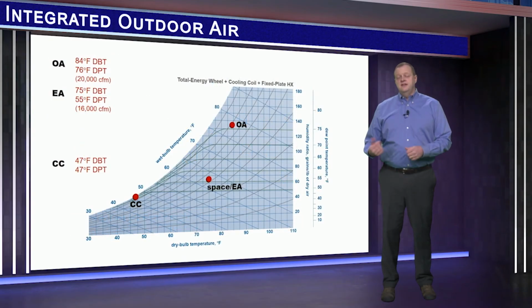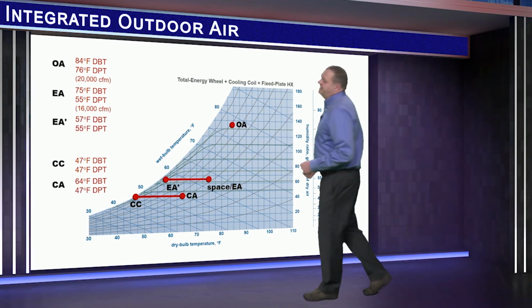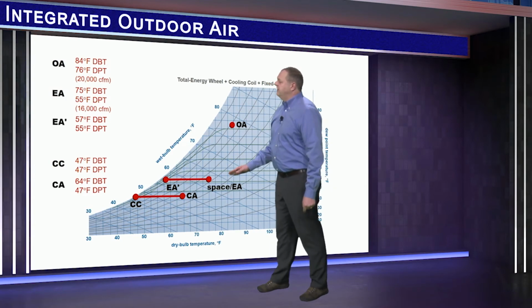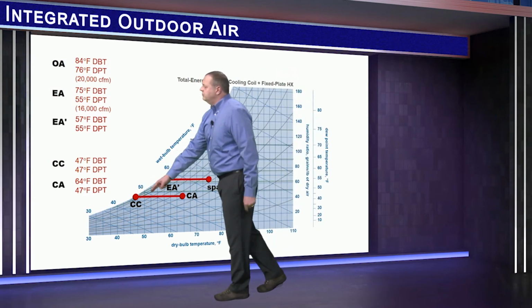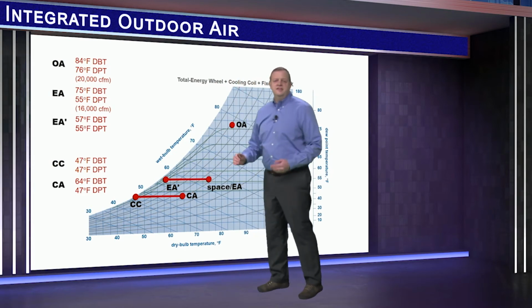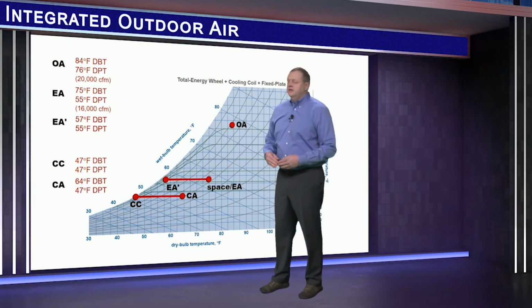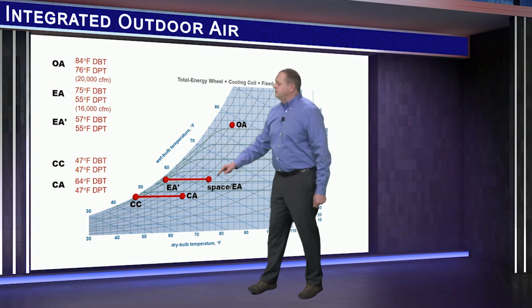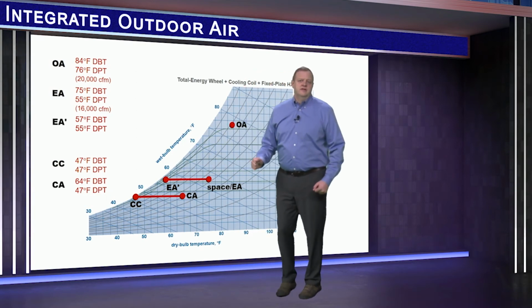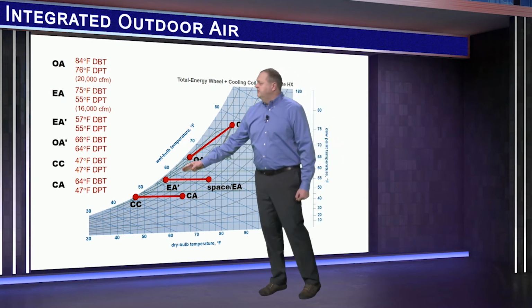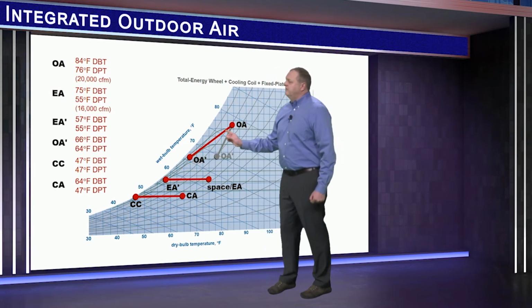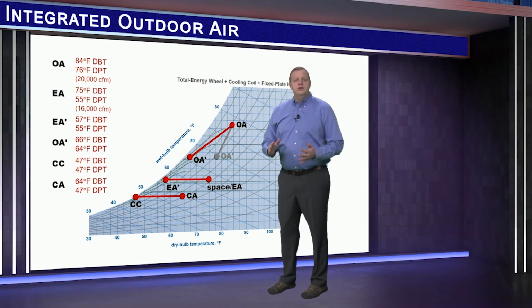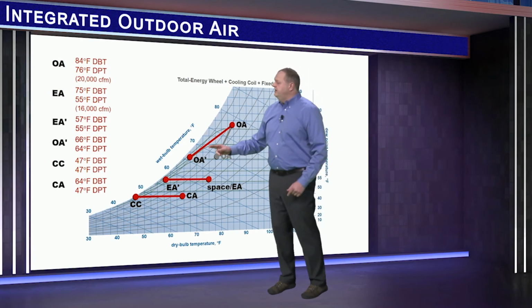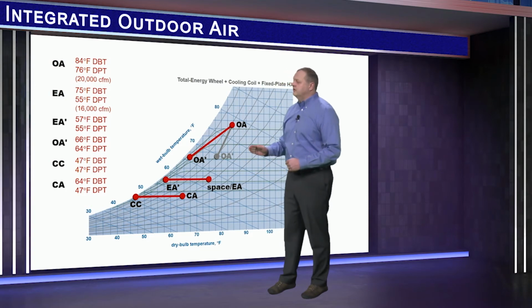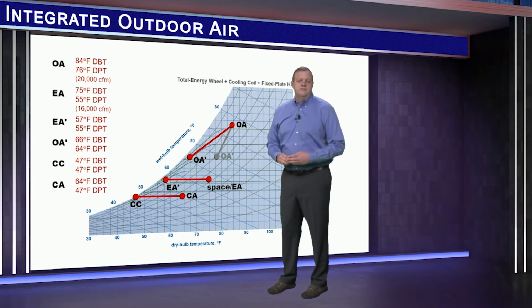The different component in this configuration is the downstream fixed plate heat exchanger. This device transfers sensible heat from the warmer exhaust airstream to reheat the cool dehumidified air to 64 degrees in our example. On the other side, this exhaust air is cooled down to about 57 degrees. Now with this cooler exhaust air, the total energy wheel provides an even greater benefit, pre-cooling the incoming outdoor air to 66 degrees, quite a bit cooler than without the downstream heat exchanger.